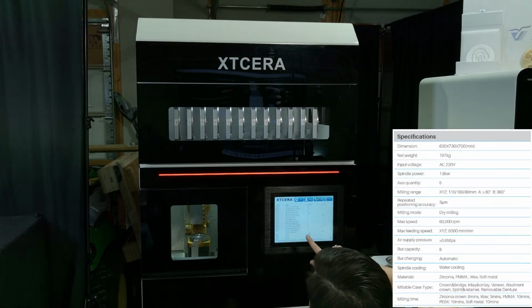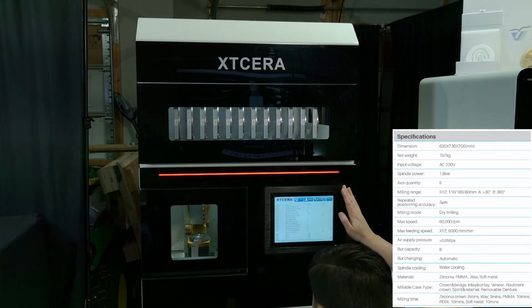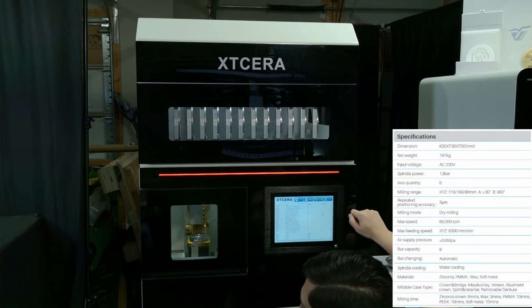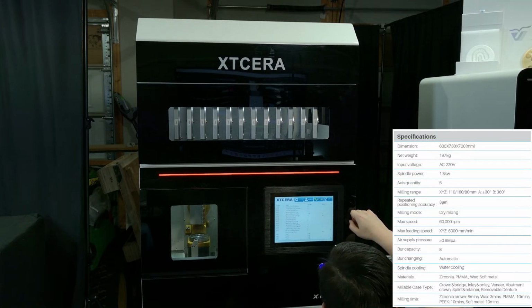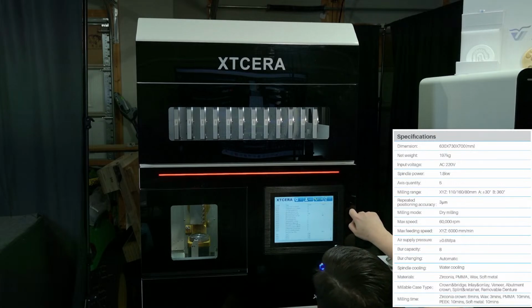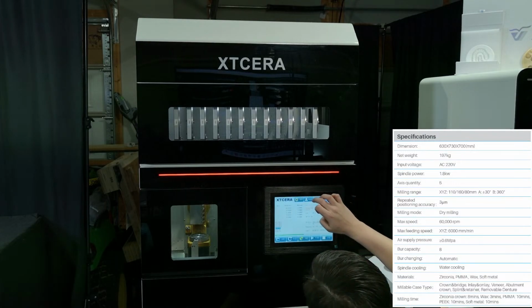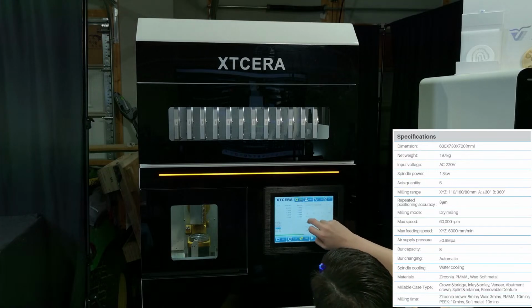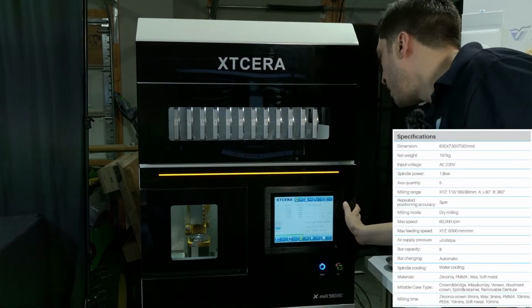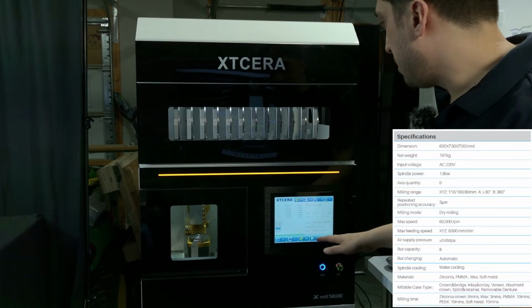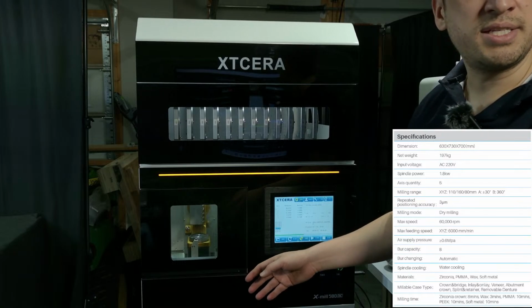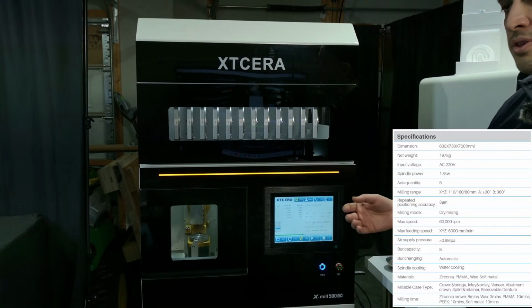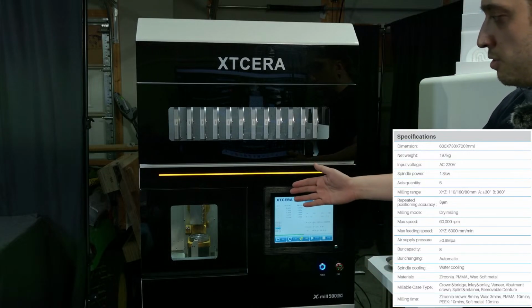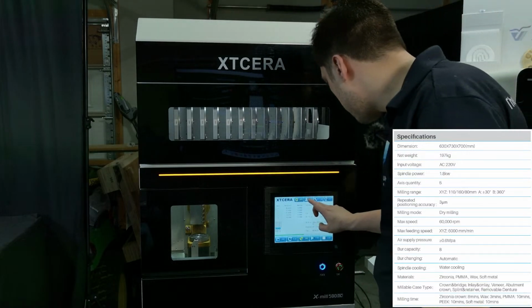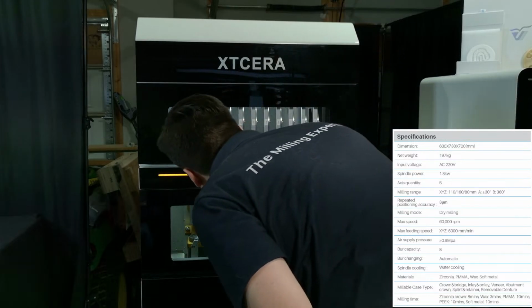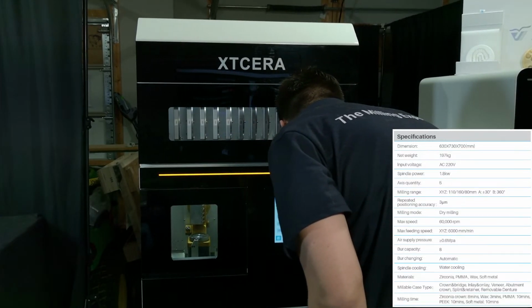So I think that because I don't have enough air to run the chuck, it's going to give me this error message. So everything's going to turn red and let me know I need to adjust my compressor. So we'll probably do that for the next stream, because I might need a slightly more powerful compressor. Didn't realize that my top end was set so low. But what we're going to go ahead and continue doing is I'm actually going to go through the calibration process, because that is something that we can do, and this is part of the normal process. So we'll go through and actually calibrate one of these. And let me get that robotic arm back up and out of the way.